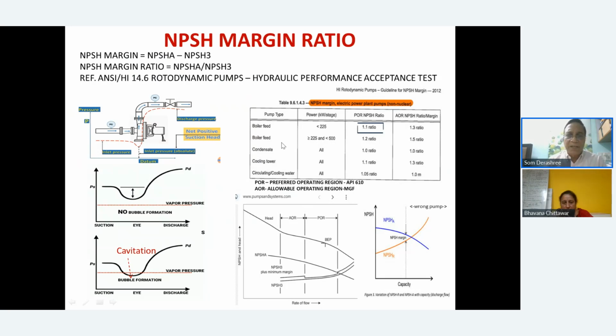They give you a table. What does the table say? For the boiler feed water pump, if the power requirement is less than 225 kilowatts, the smaller pumps, then for the preferred operating region, this is POR, the ratio should be 1.1. And if it is AOR, the allowable operating region, it is 1.3.